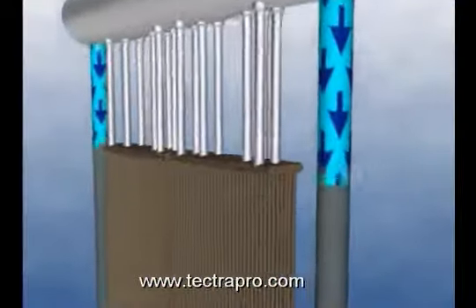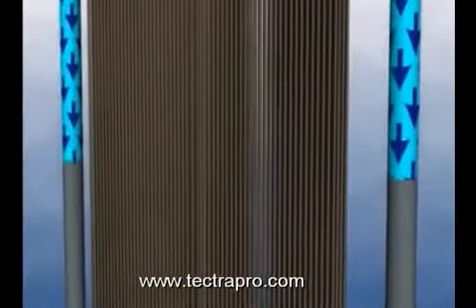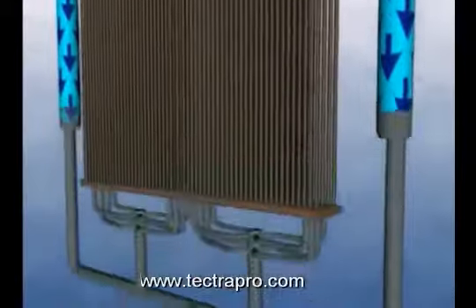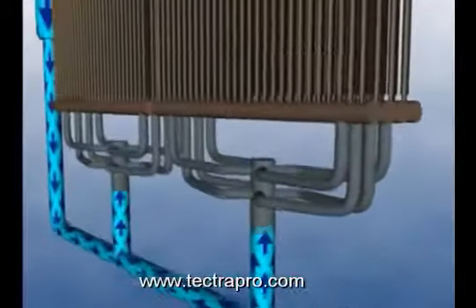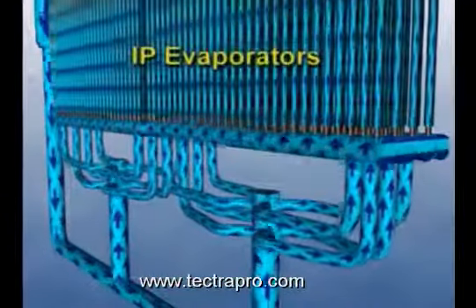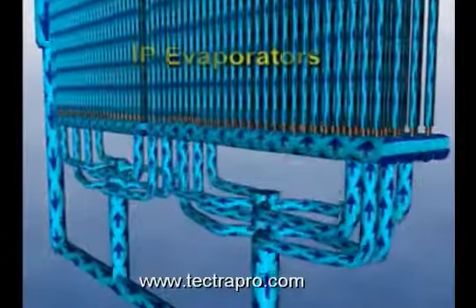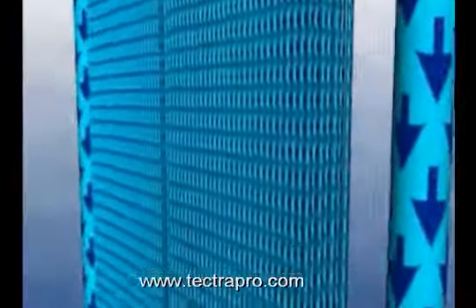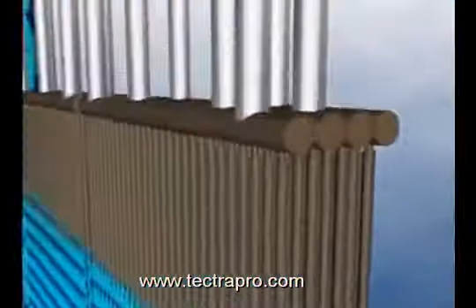Water flows from the IP drum down the risers and through 4 IP evaporator racks. Due to the difference in density between the water in the downcomers and the steam-water mixture in the evaporator and risers, the lighter steam and water mixture returns to the drum.